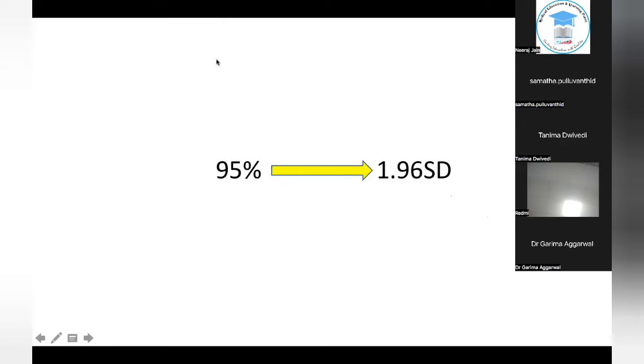Suppose you tell them, see, at this level of bilirubin, our control values over the last 6 months of data are showing an SD of 0.2. That means measurement uncertainty 0.4. Whatever we are reporting as 22.4, I can say with 95% certainty, the maximum value possible is 22.8. According to me, you can wait for some time, then get this bilirubin done again, and you can take the decision accordingly. Then the clinician will also understand. They have also read this statistics in their textbooks, Park and Park or in other references.